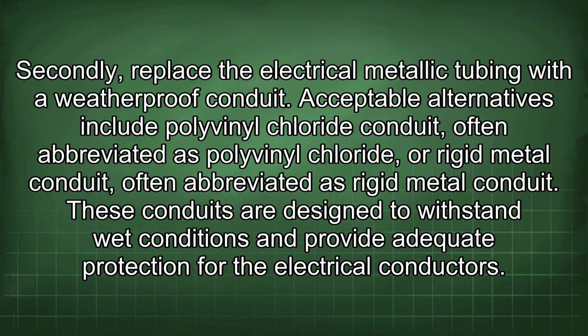Secondly, replace the electrical metallic tubing with a weatherproof conduit. Acceptable alternatives include polyvinyl chloride conduit, often abbreviated as PVC, or rigid metal conduit, often abbreviated as RMC. These conduits are designed to withstand wet conditions and provide adequate protection for the electrical conductors.